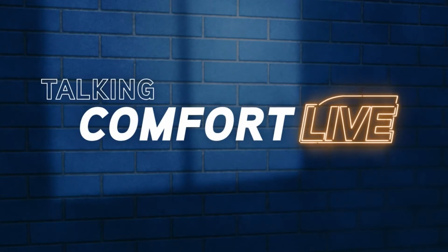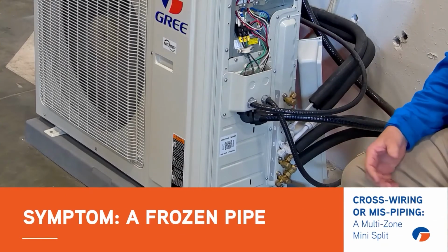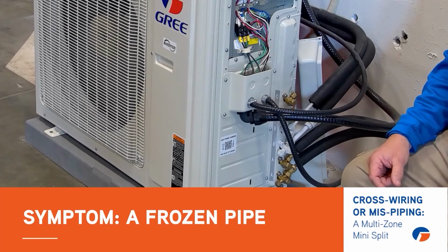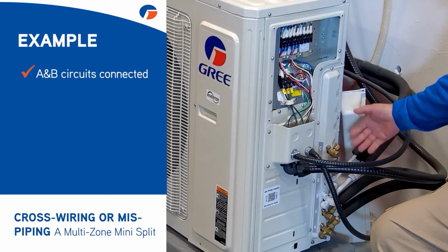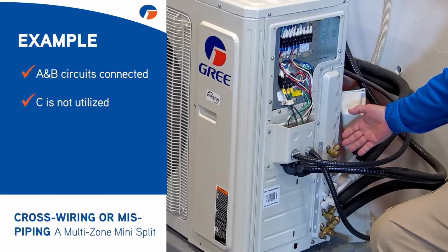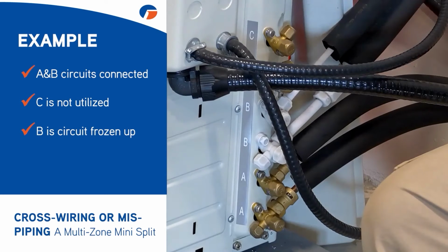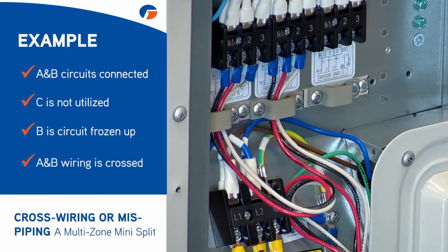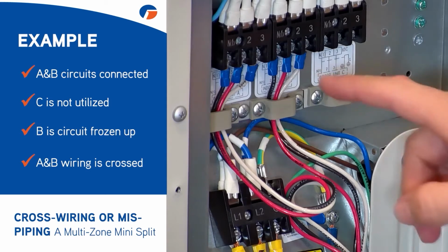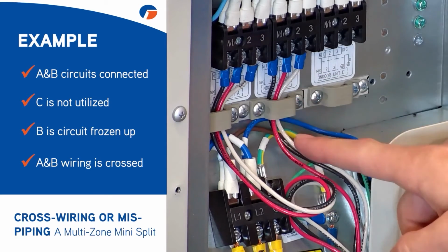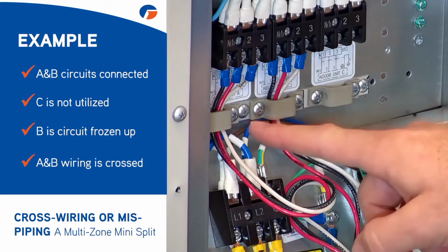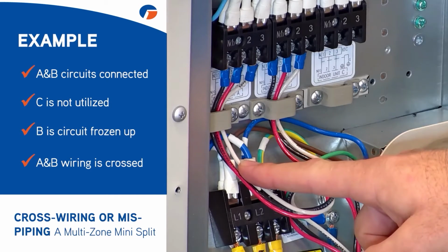Today I want to talk about multi-zone mini splits and what happens when we cross-wire or mispipe the outdoor unit with multi-zone systems. In this system that I've got running here right now, it has 2 circuits, both A and B hooked up. C is not utilized. And as you can see, the B circuit's froze up. The reason why that circuit is froze up is because up on the terminal blocks, A and B wiring is crossed, meaning our piping from our indoor unit going to the A circuit, the wiring from that head is going to B, and the piping that's going to the B circuit and the wiring from that is going to A.